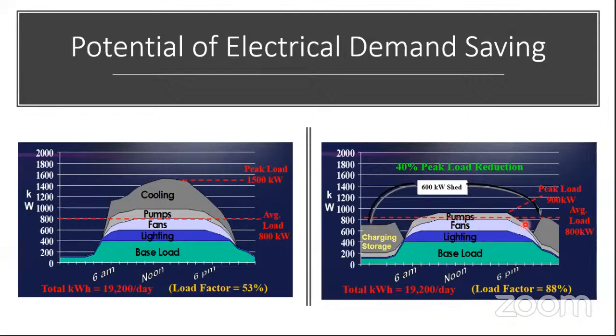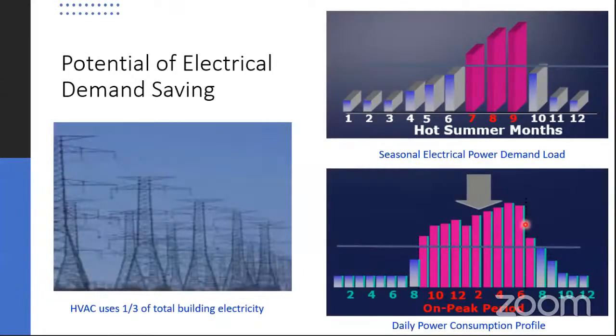So the idea here is to see how we can cut down on our connected load. That is how we save on demand. We could also see this from the perspective of around the year. These are 12 months, and it's generally during the hot summer months when the load is peak. In the other months, the load is not that much. But we still tend to install chillers of a very high capacity, of the peak capacity in general.